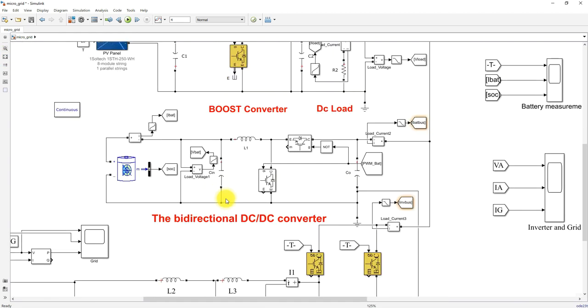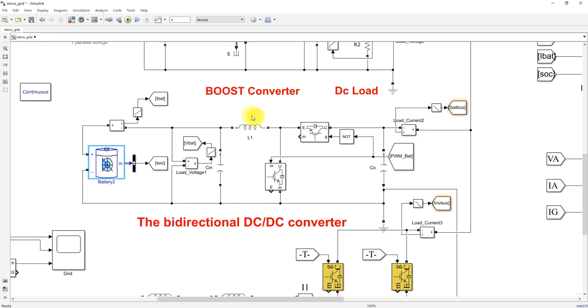Here we have the battery energy conversion system. The battery is rated 12 into 20 volts — that means 20 twelve-volt batteries — with a capacity of 48 Ah. It is connected via a bi-directional converter, and the current flow will be in both directions. Based upon the power balance in the system, this bi-directional converter is for maintaining the DC bus voltage at 400 volts, controlled by means of a voltage control method.